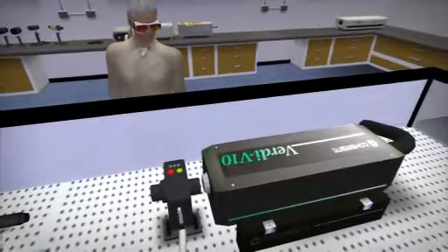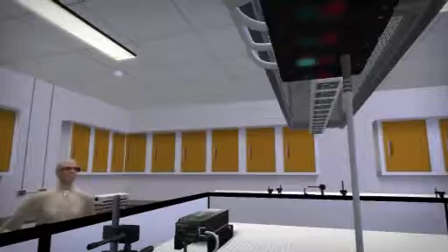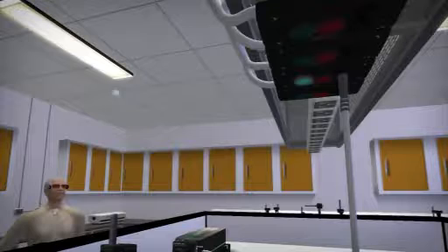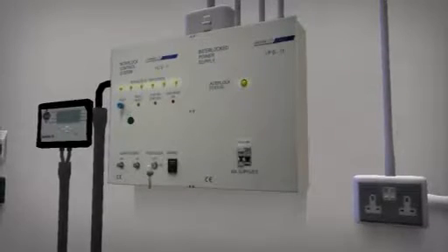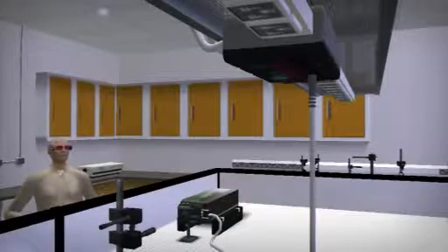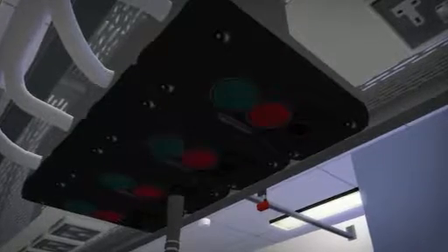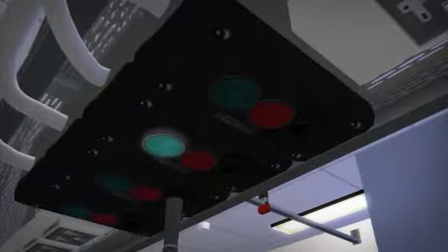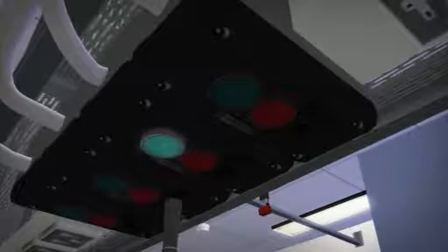The laser itself is activated by a key-controlled power supply box, which may also be connected to the central interlocking system. The control box near the door entrance powers remote interlock switches located around the lab. These control separate beam shutters and make-break relay sockets, of which any laser of class 3B or 4 must have according to laser safety standards.